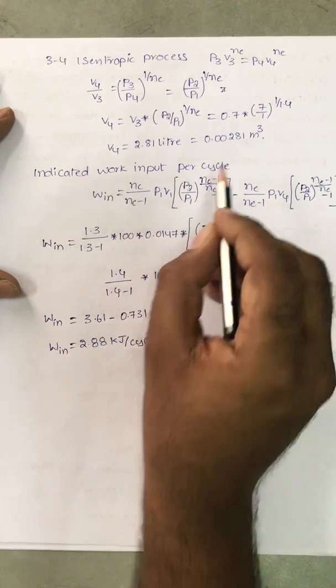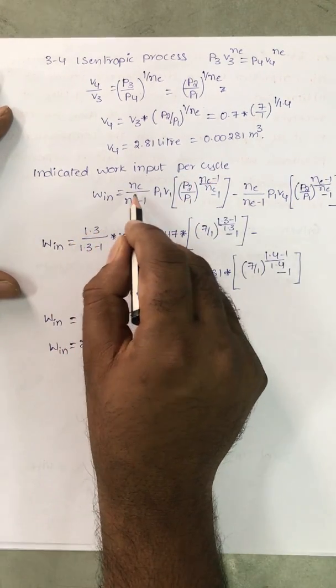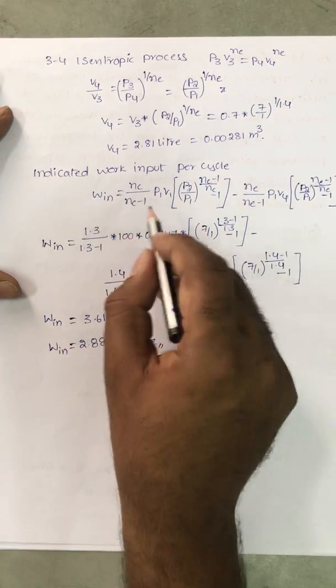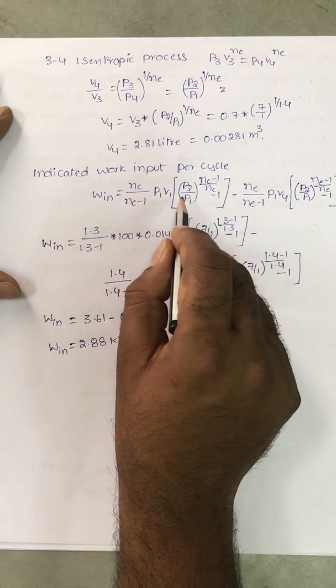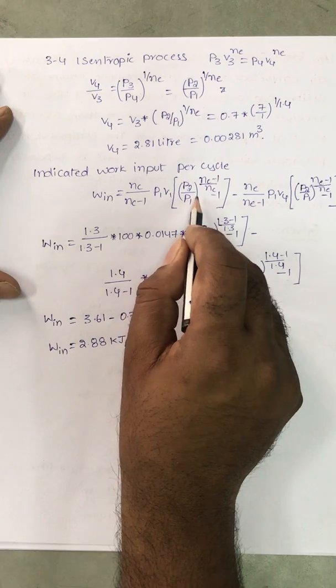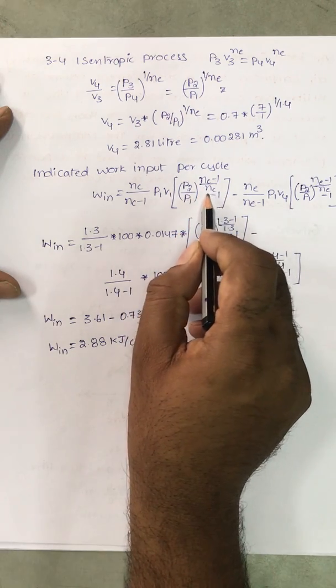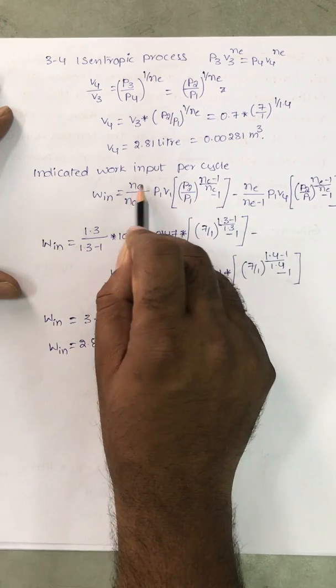Indicated work input per cycle: W indicated is compression work minus expansion work. The formula is N by N minus 1 P1 V1 into P2 by P1 all power N minus 1 by N. If it is compression, use compression index.